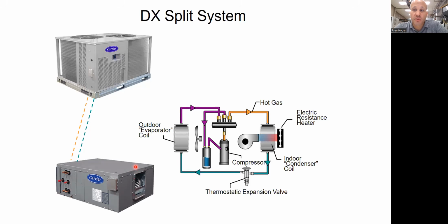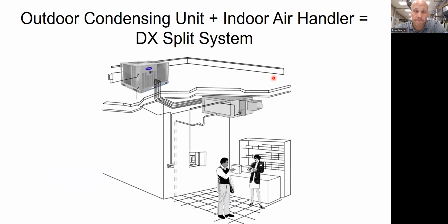If I want to make this into a heat pump version, I need to get an outdoor unit that has a reversing valve in it, just like we talked about on all the other types of systems. I need that reversing valve. That would make it a heat pump system. There are other components, slightly different controls for defrost and things like that, an accumulator inside, but the only moving part really is that reversing valve, right? And then I can make this into a heat pump version of that.